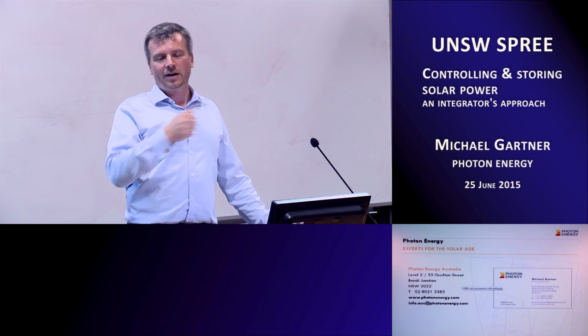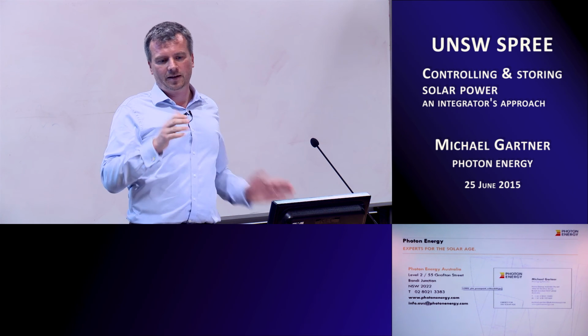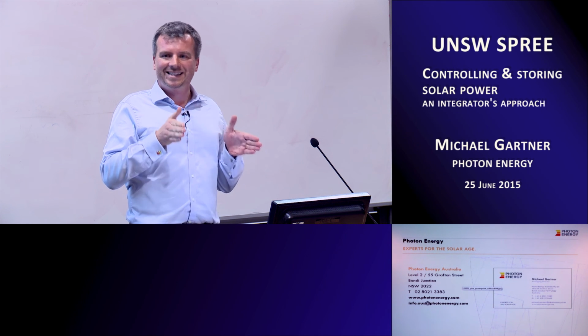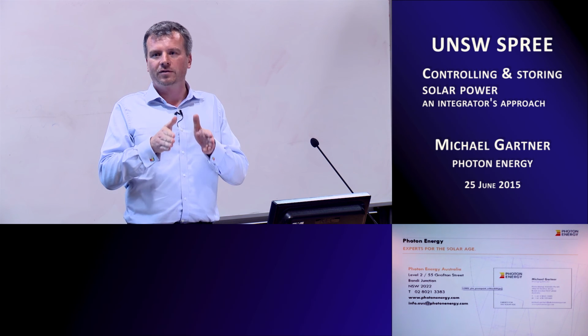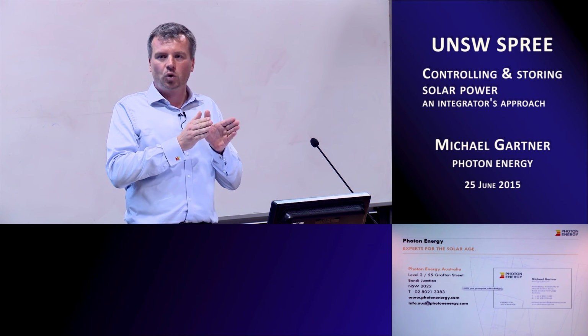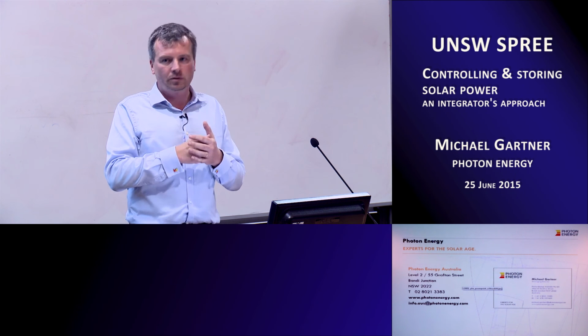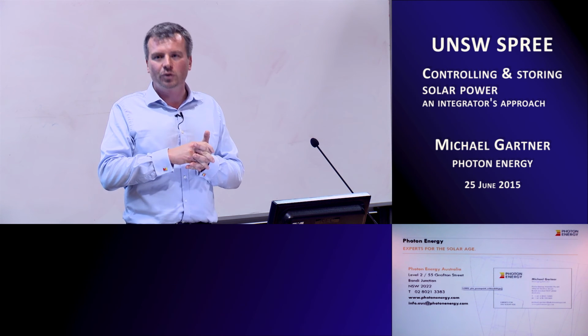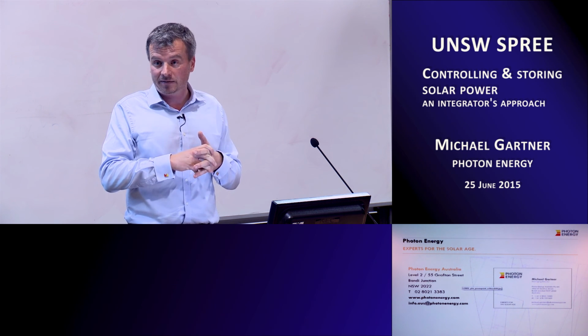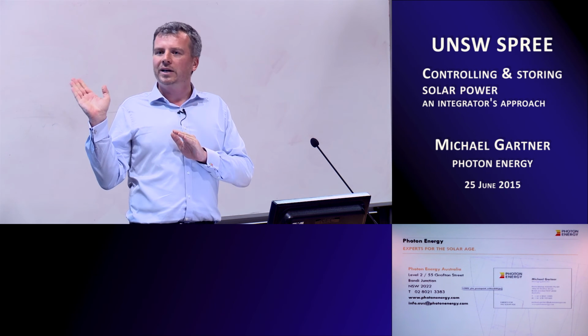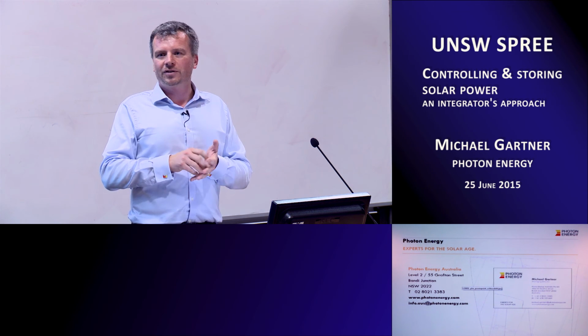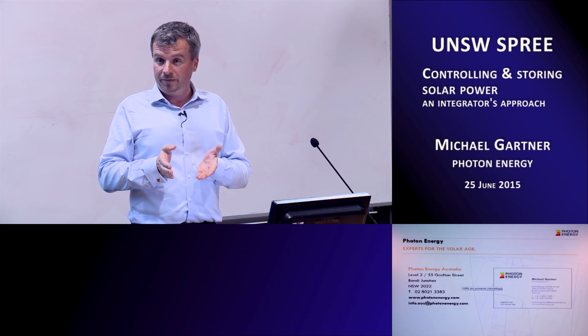So at that point, when we dimension the system, we'll consider that in the choice of technology. If we're doing a lot of quick charges and discharges, we won't use lead acid, because it becomes increasingly less efficient quite fast. But in the sort of situation we're in, we're getting a round trip efficiency over 80%, which is still quite good.